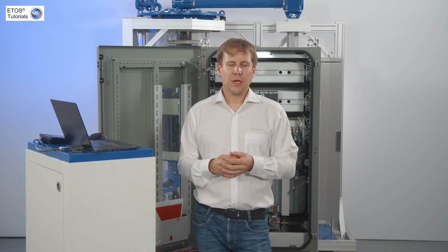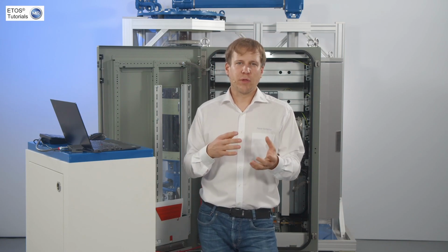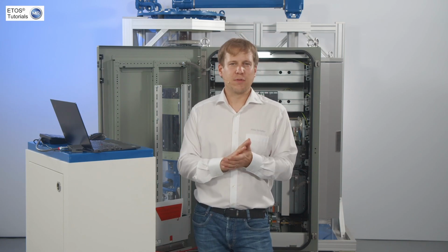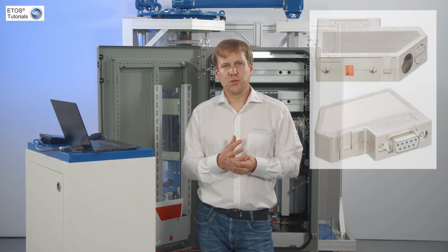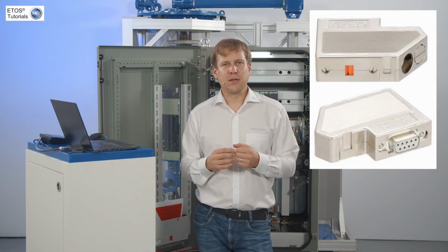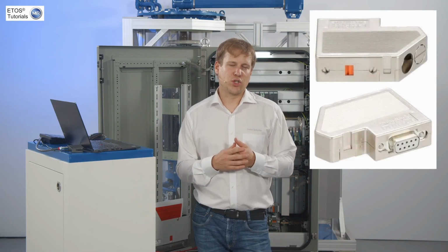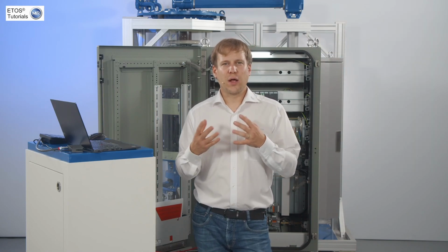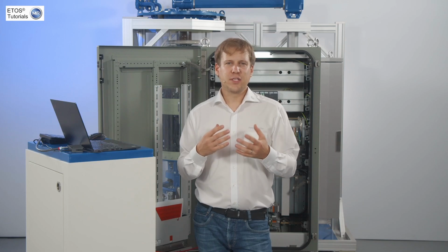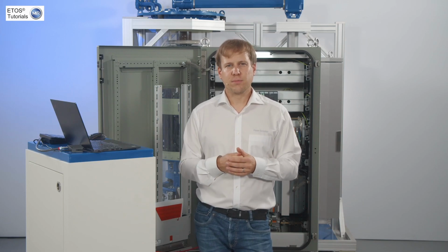Number 9. Some of the units have more than one CAN bus communication card. That means there's more than one DIO module or even some other modules that require CAN bus communication. If that's the case, we sometimes use connectors with built-in resistors for termination of the cables. That needs to be in the right position, otherwise that could also disturb the proper communication.